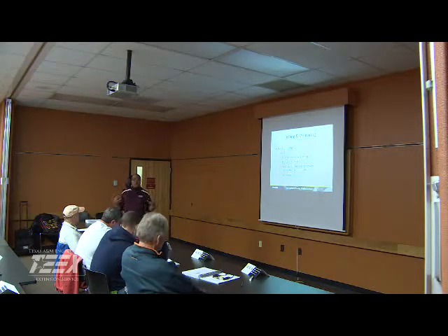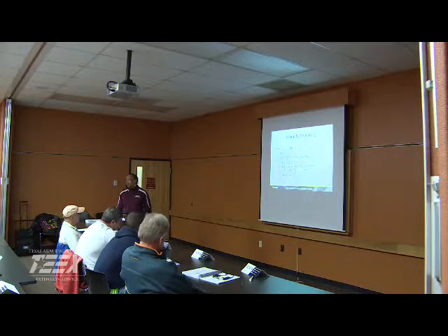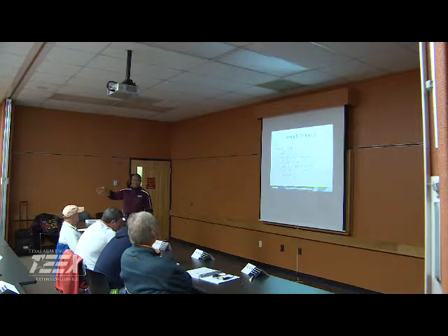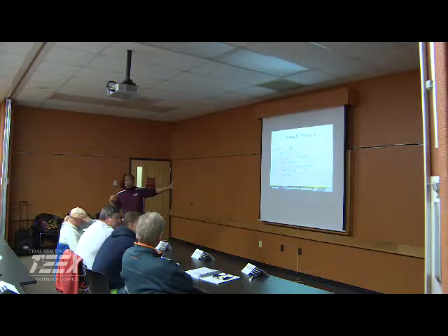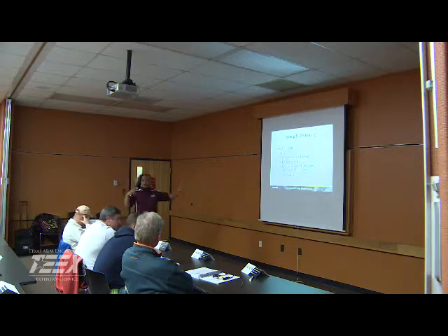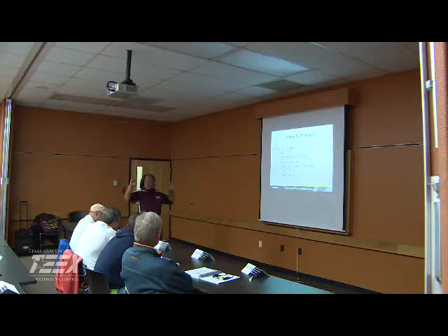So how do we rectify? How do we minimize pumping sand? Develop it properly. Excellent. What else? Make sure you have the right screens, the right gravel. Excellent. You want to repair any deficiency. If you have corroded or broken screens, make sure it's the correct size.